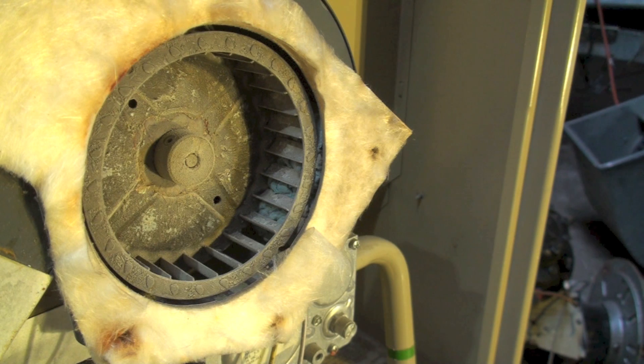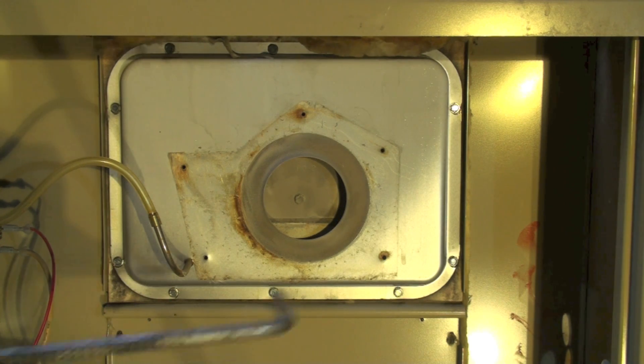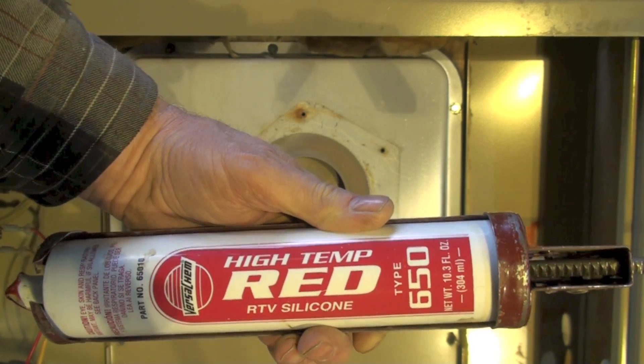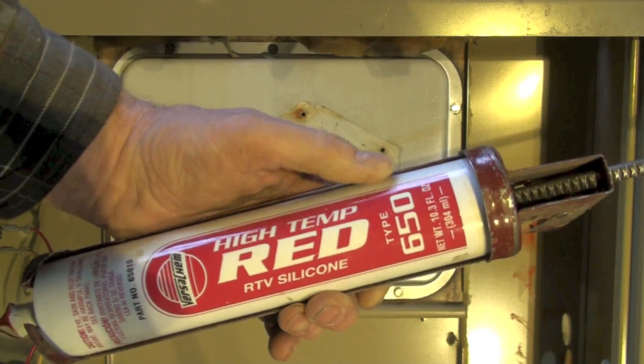So if I'm going to put this back on — let's say I found a bird in it or something — what do I do next? I've pulled off the gasket material here, it's kind of a fiberglass stuff. I don't necessarily use a gasket; if one comes with the part I'll use it, but this is what I use: just high-temp sealant. It works fine, it's good for the temperature, and it's a gasket all by itself.